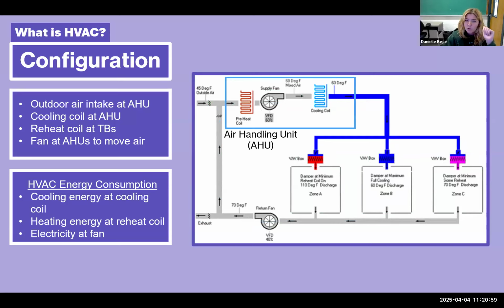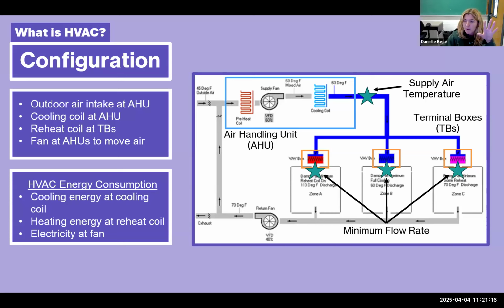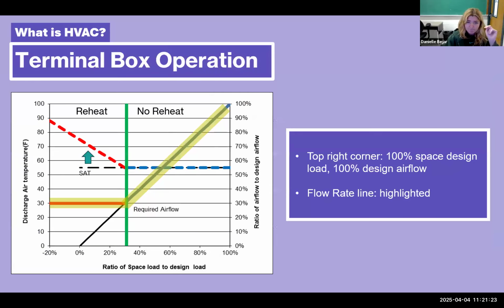The two pieces of equipment that we're really going to be focusing on are the air handling unit and the terminal box. More specifically, we're going to be manipulating the supply air temperature, that's the temperature after the air handling unit. And we're going to be changing the minimum flow rate, that's the air flow rate at each of the terminal boxes. Those are the two things we're manipulating. And just to understand a little of terminal box operation, I'm going to bring up the little laser pointer. We're changing the minimum flow rate.